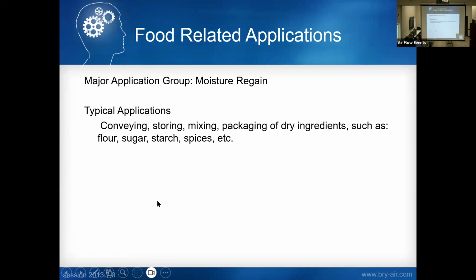Hey, Walter, is the wheel size driven by the dehumidification or the airflow required? So we try to design the wheel based on the dehumidification requirement. So we'll do a lot of applications that require more cooling, and we have face and bypass humidity control, but we'll do a constant bypass of a certain amount of air if we need more airflow for temperature control. Okay, that makes sense. Keep the rotor again as small as possible.